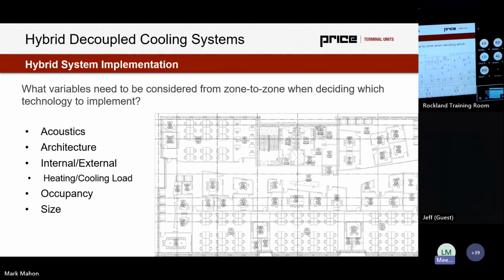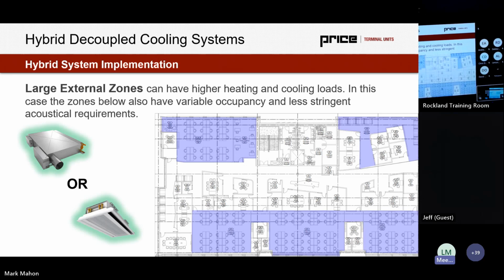But they really were struggling with where and how they were going to lay out each option from a zone to zone perspective. They were evaluating architecture, what the architect actually wanted to see, evaluating the actual heating and cooling load and whether the zone was internal or external, how many occupants and how variable it was, what the square footage was, and then how loud the space was going to be as well. And so I'd given my own recommendations, and I want to review those and talk through with the group why I made those recommendations and also get some feedback from the room as to what I might have suggested. So starting with the larger external zones.